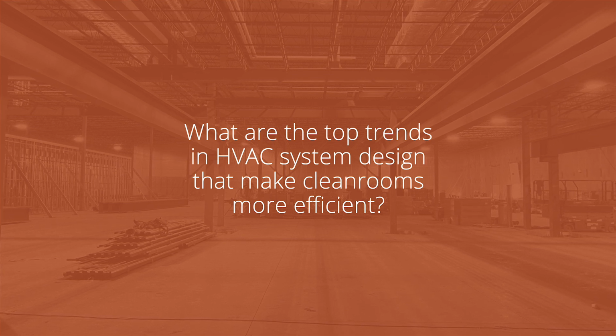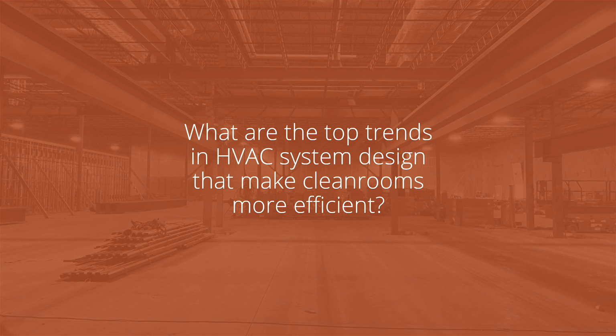What are the top trends in HVAC system design that make clean rooms more energy efficient? So I think there's a few trends, but the top trend is probably to do a performance-based strategy where you measure particles in specific spaces within the room or over a representative grid in the room, and then you can reduce the amount of airflow or air changes based on that performance requirement. So as long as there's a space within the suite that doesn't require more air, you can reduce that airflow. And if there are areas that actually require a little more airflow, you can adjust that over time.